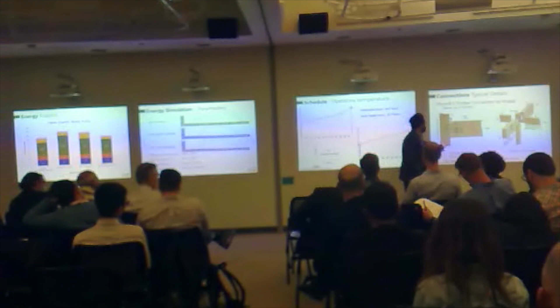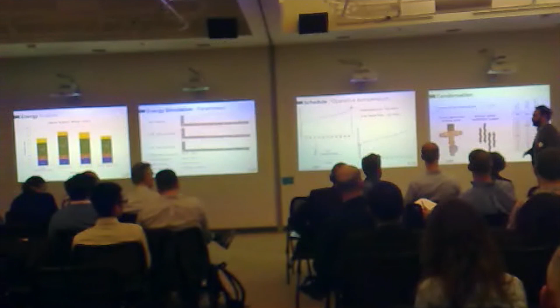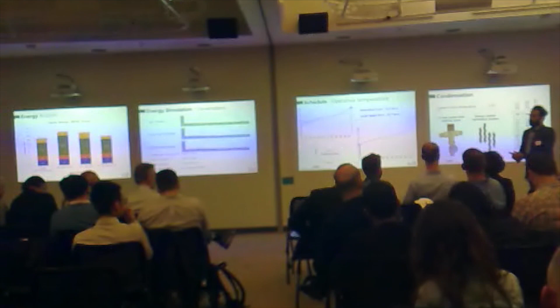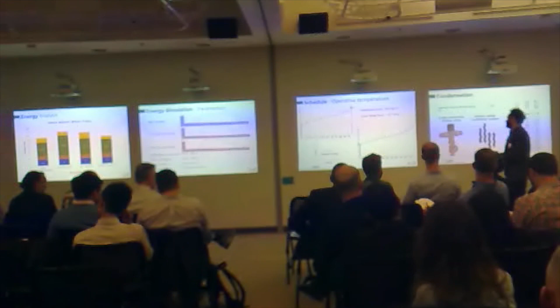And like let's talk about the elephant in the room, condensation. When the radiant is involved, it's the biggest issue. As per our simulations, the surface temperature in the building never goes below 17.8 degrees Celsius. And for the worst case scenario, in our building, relative humidity 84, our dew point temperature will be 15 degrees Celsius. So as per the simulations, we should not be dealing with dew point condensation in our building. But as John mentioned, that simulations can be either 50% or even 100% wrong. So we went for a 3-way motorized mixing valve at each pair of manifolds, and we have an always active ventilation system. And this is the carbon dioxide concentration in various parts of the building, and it's below 900. It's good because it's considered for 100% occupancy at all times.